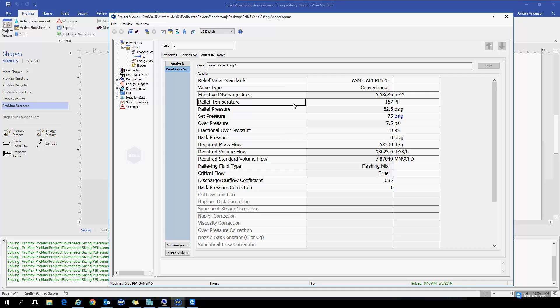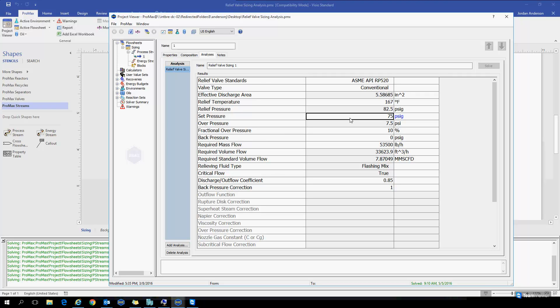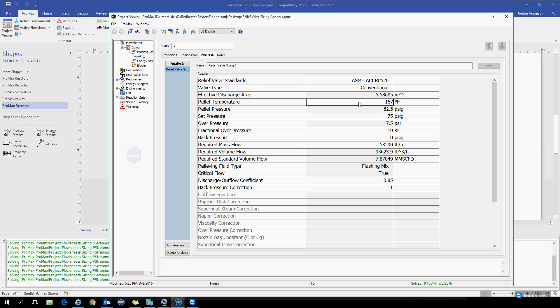Continuing down our list of properties here, relief temperature is another property that we'll need to define. This is the temperature that your contents will be at, at relief pressure. This temperature is not the temperature at your set pressure, but it's the temperature increase that will be expected as the pressure increases up to your relief pressure, and so that value needs to be input by us.